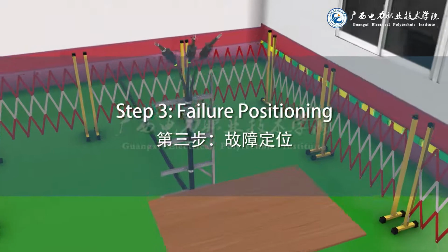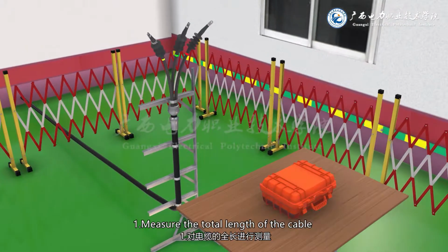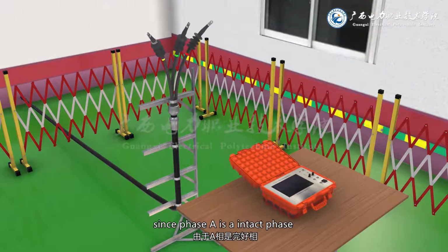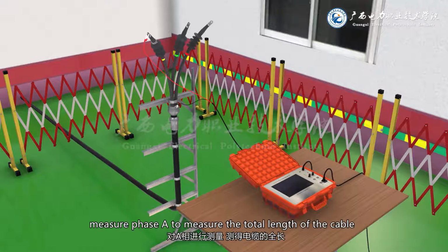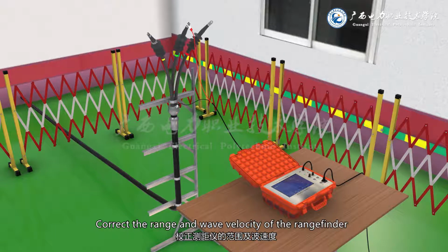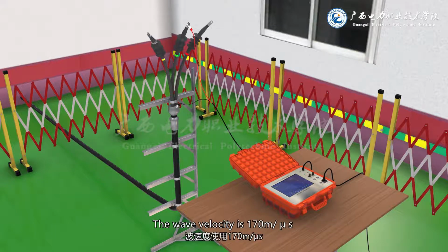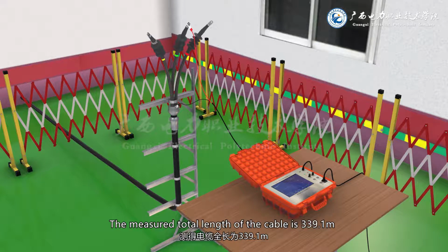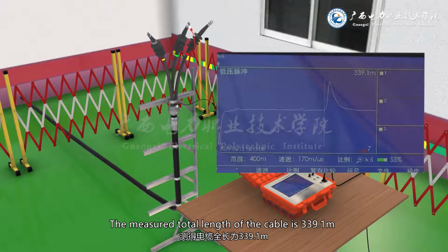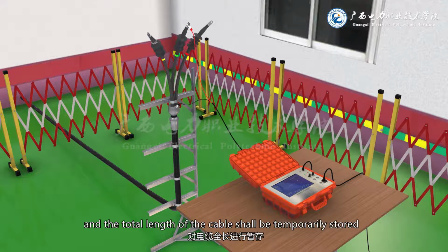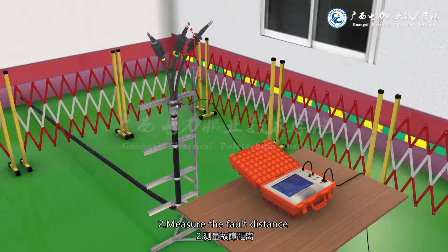Step 3. Fault positioning. 1. Measure the total length of the cable. Since phase A is an intact phase, measure phase A to get the total length of the cable. Correct the range and wave velocity of the rangefinder. The wave velocity is 170 meters per microsecond. The measured total length of the cable is 339.1 meters, and the total length shall be temporarily stored. 2. Measure the fault distance.